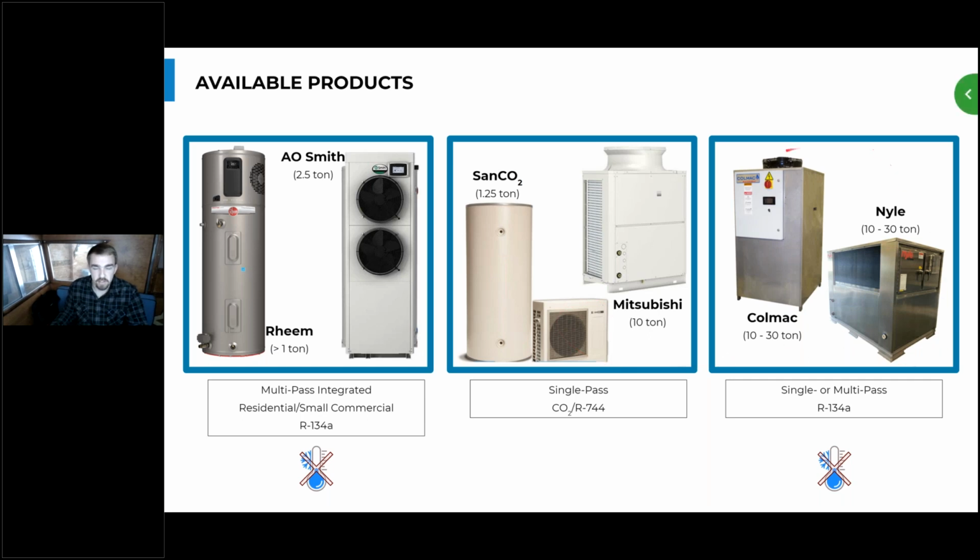So these actually originated in Hawaii. So they were designed to just put on the rooftops and buildings in Hawaii and always operate in 70 or 80 degree weather. And they operate really efficiently there. So more tropical installations outside really make this equipment shine, but they can also work really well in applications like Jackson, where they're in a semi-buffered space so they don't see air temperatures below about 40 degrees.